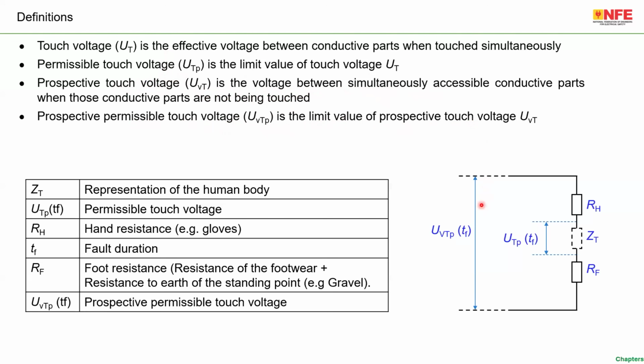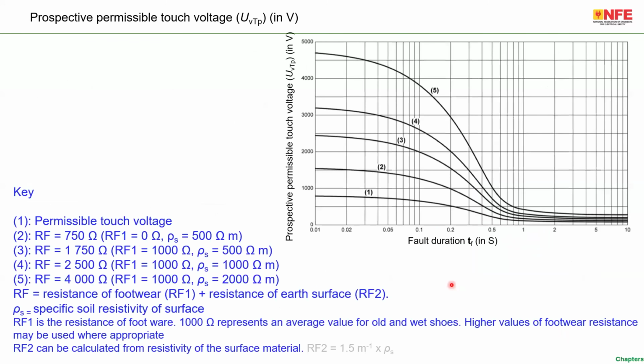I am just explaining this to inform you that during evaluation of a substation, the earth electrode or the touch voltage testing of a substation, all these values are required or to be considered. For example, the glove resistance and the shoes resistance, we can simulate in software, or we can even calculate it in a practical condition. For example, this one, figure number 1, is the IEC 61936 recommended permissible, tolerable limit of the touch voltage without any additional resistance. That means there are no gloves, no shoes. You have already seen this particular graph, figure number 1.